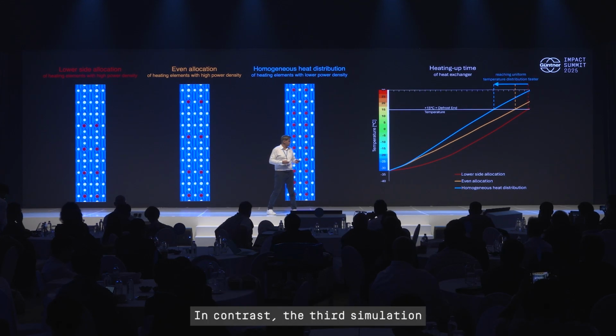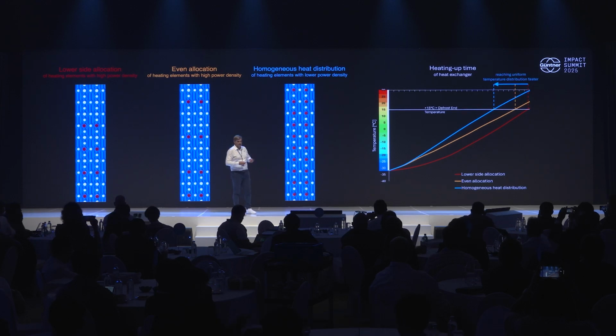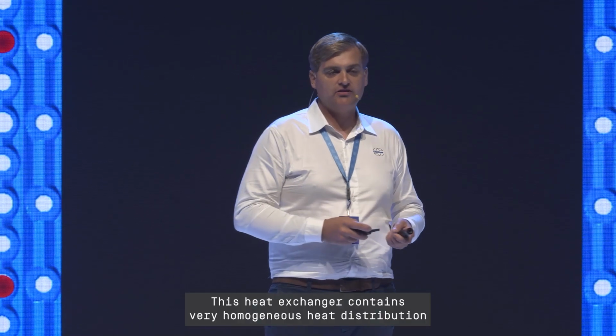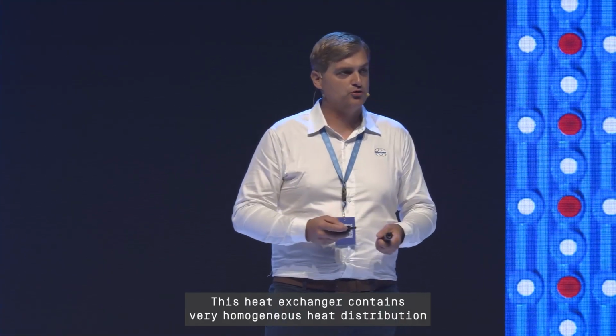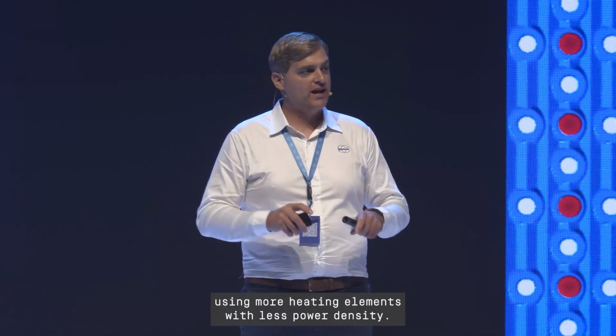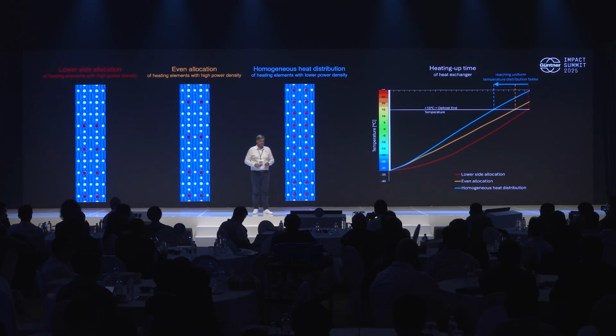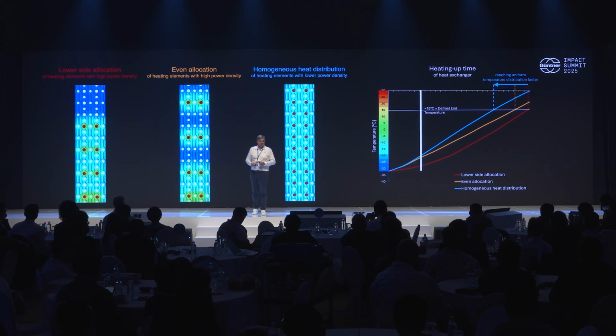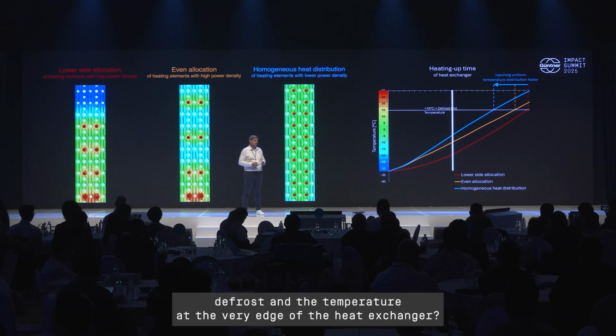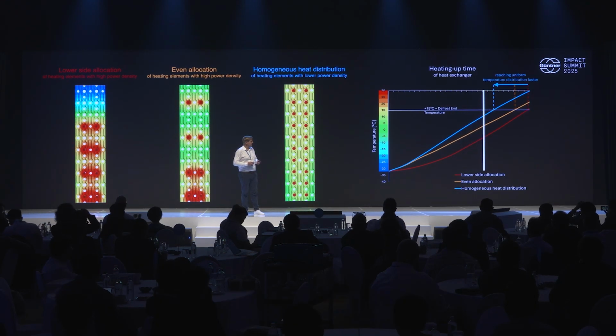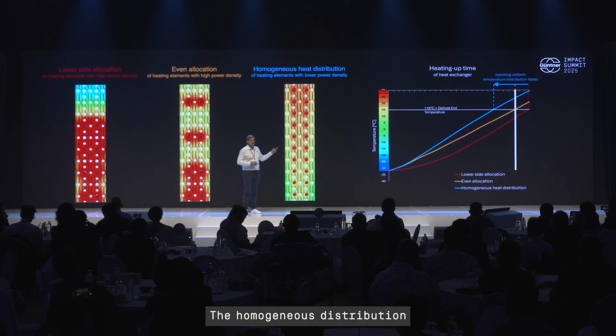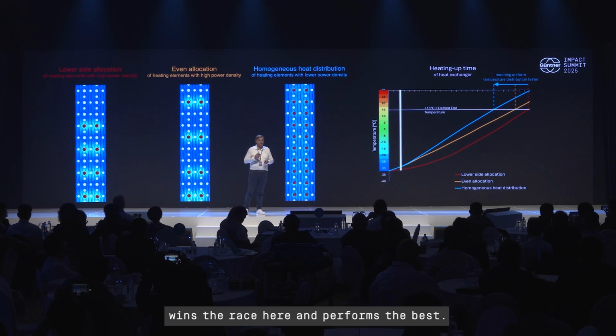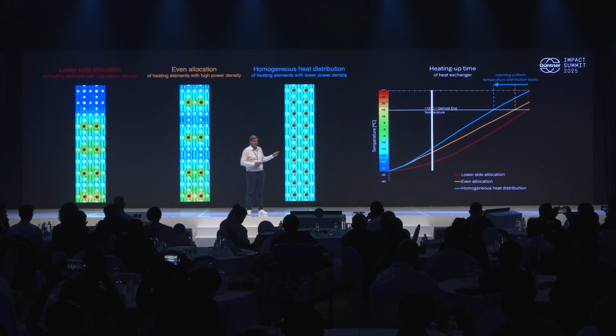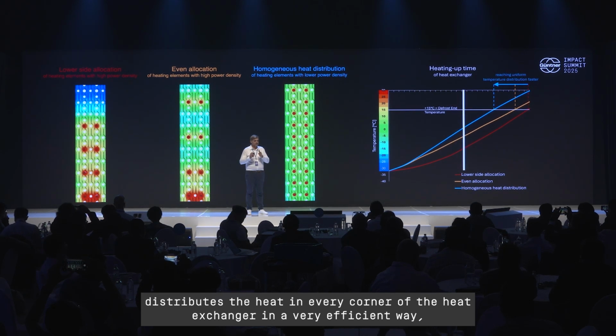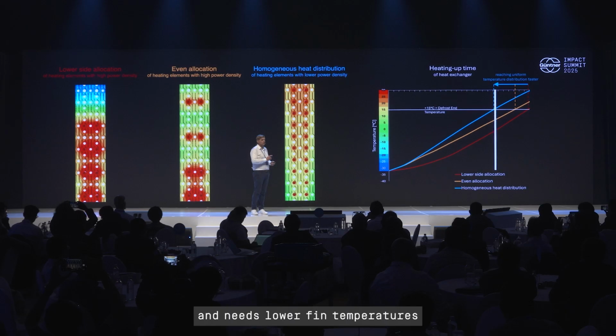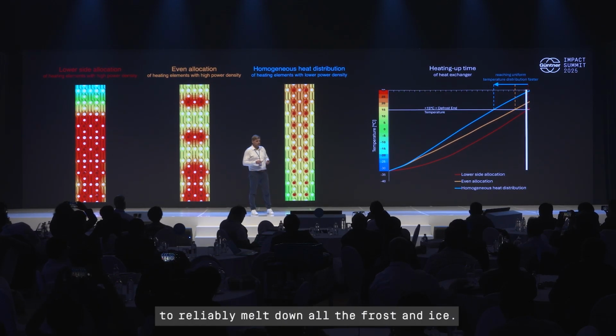In contrast, the third simulation, here in the middle, shows a different approach. This heat exchanger contains very homogeneous heat distribution using more heating elements with less power density. Let's compare their defrost time - how long will it take them to reach defrost end temperature at the very edge of the heat exchanger? The homogeneous distribution wins the race here and performs the best. It defrosts faster, distributes the heat into every corner of the heat exchanger in a very efficient way, and needs lower fin temperatures to reliably melt down all the frost and ice.